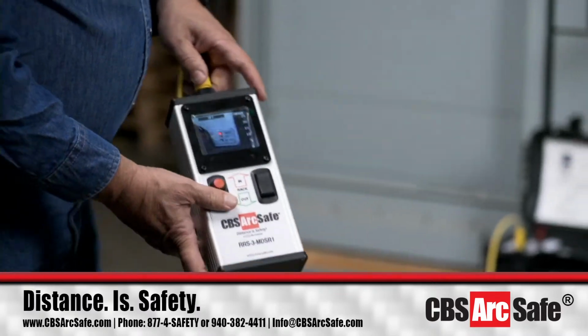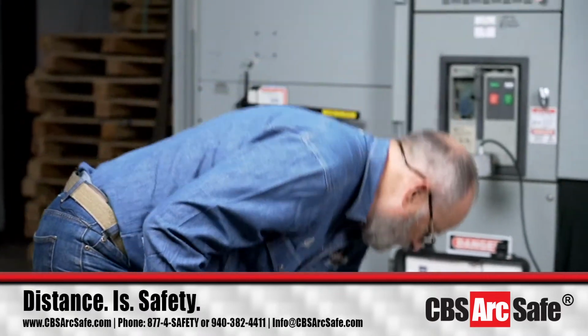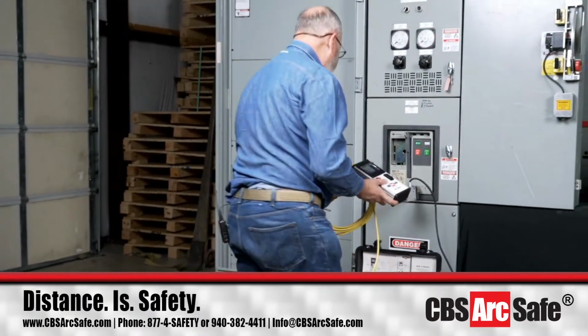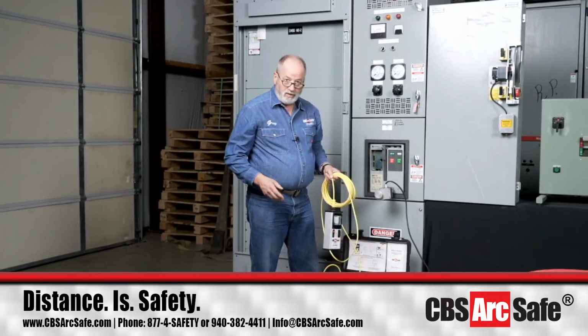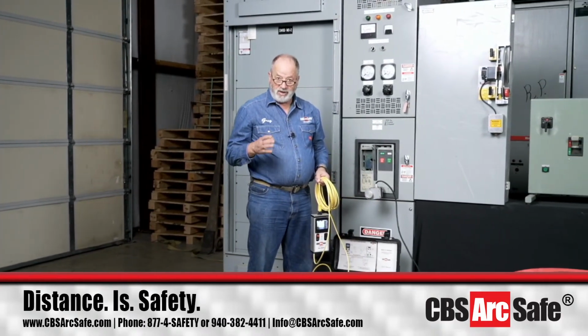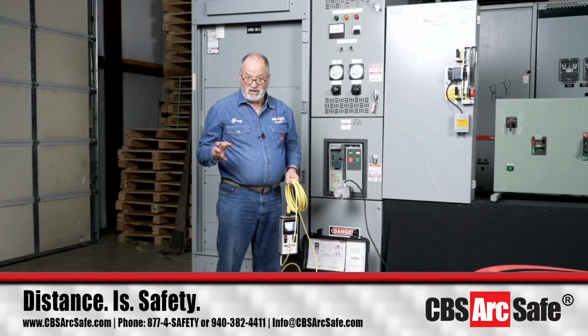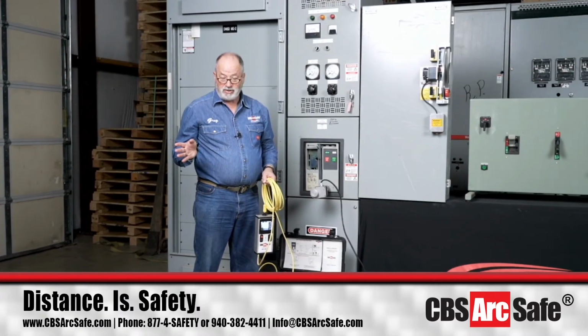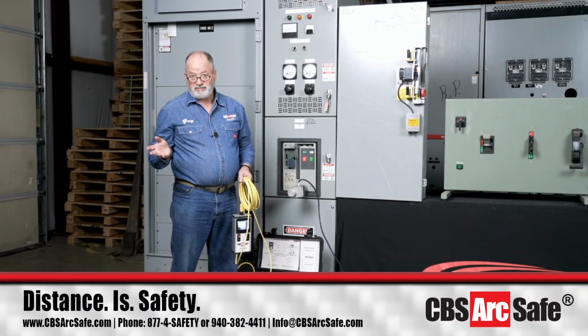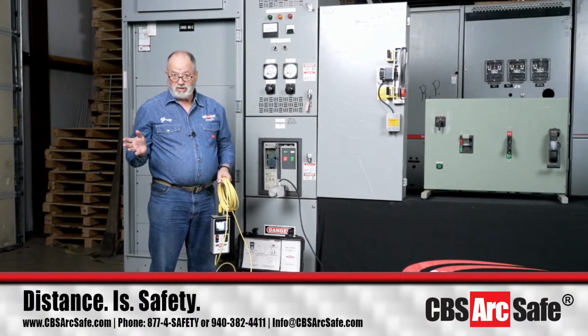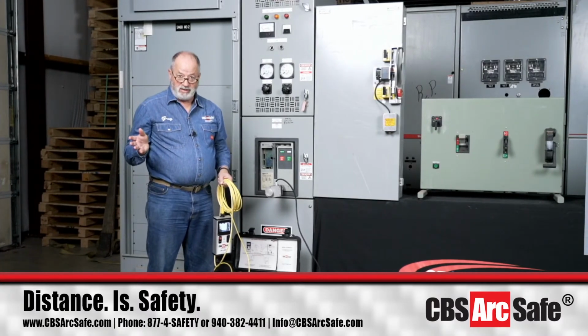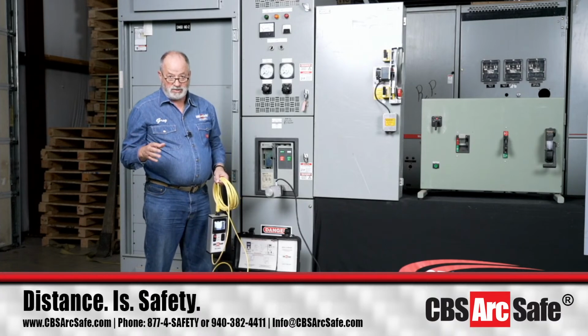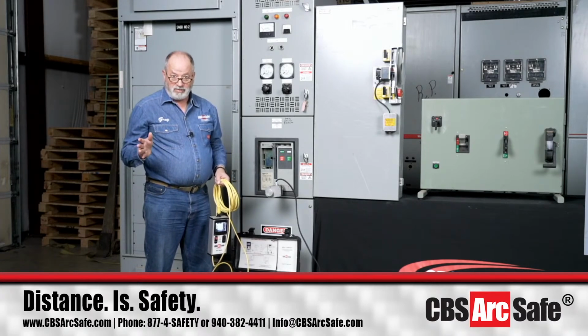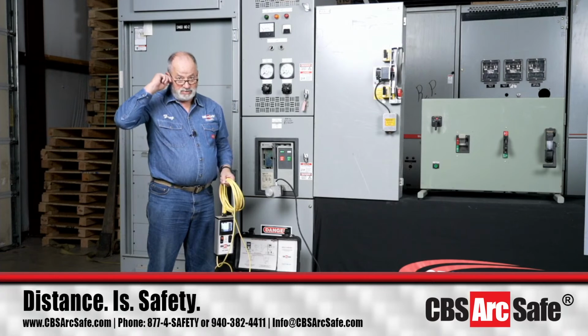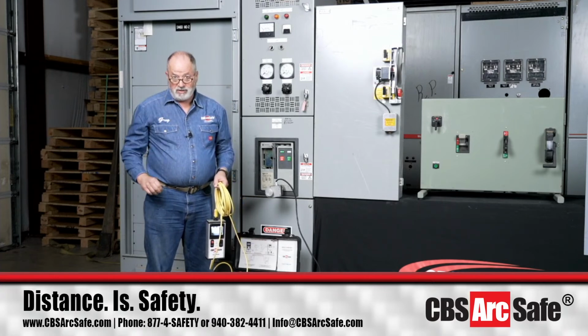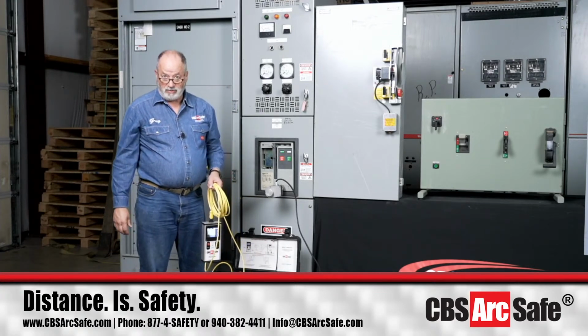Okay, that's the process. Now, one thing to note is this system is capable of racking all of the frame sizes from the 800 amp up to the 6300 amp IEC rated breakers. Domestically, we'd see the 4000, 5000 amp breakers. We know some of our competition has problems doing anything above the 3200 amp breakers. So if you've got those big double-ended substations and data centers, this is the item you're really going to want to deal with those things.